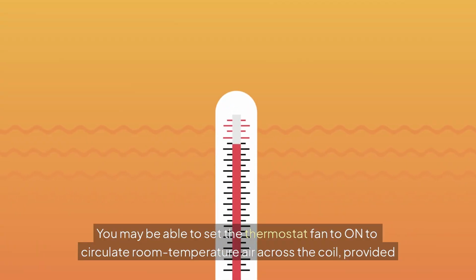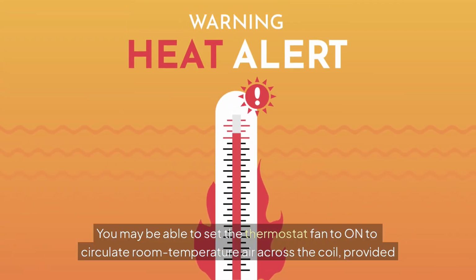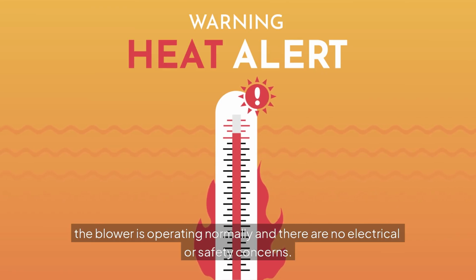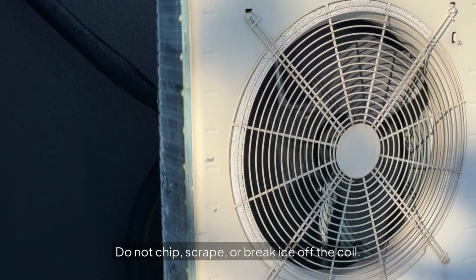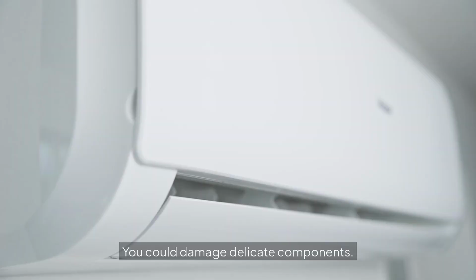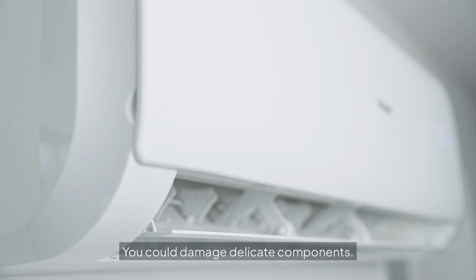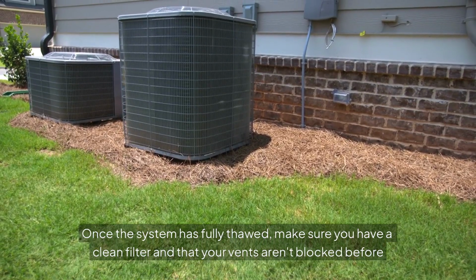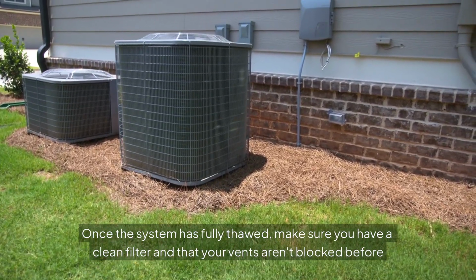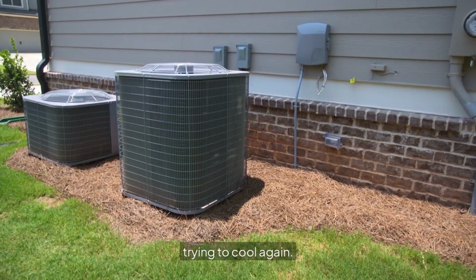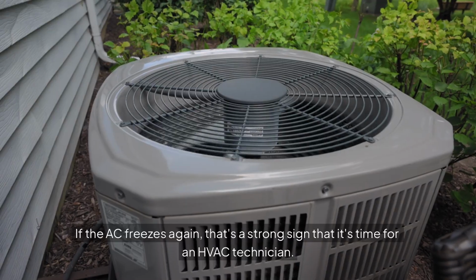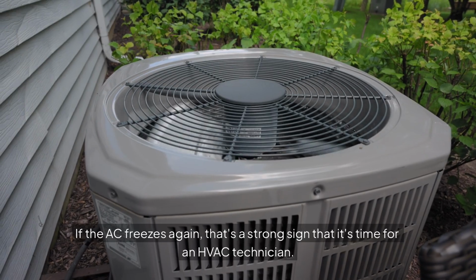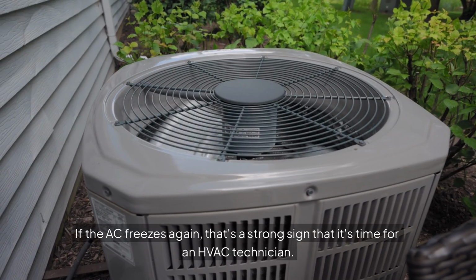You may be able to set the thermostat fan to on to circulate room temperature air across the coil, provided the blower is operating normally and there are no electrical or safety concerns. Do not chip, scrape, or break ice off the coil. You could damage delicate components. Once the system has fully thawed, make sure you have a clean filter and that your vents aren't blocked before trying to cool again. If the AC freezes again, that's a strong sign that it's time for an HVAC technician.